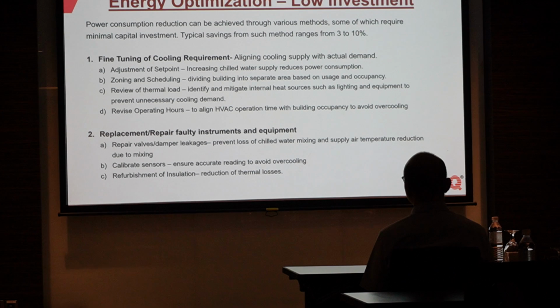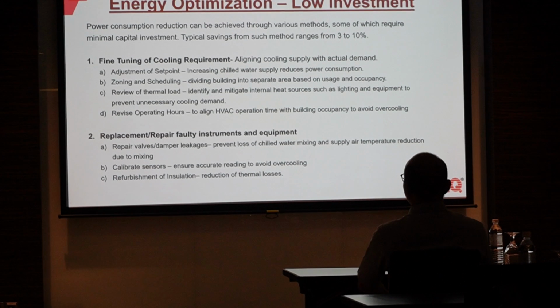Next is zoning and scheduling - dividing buildings into separate areas based on usage and occupancy. In KL downtown, there are multiple offices, and actually office space in KL is oversupplied. So there are some areas that are vacant, but you still supply aircon to them because there's no control. There are things like control dampers that you can install to prevent this overcooling.